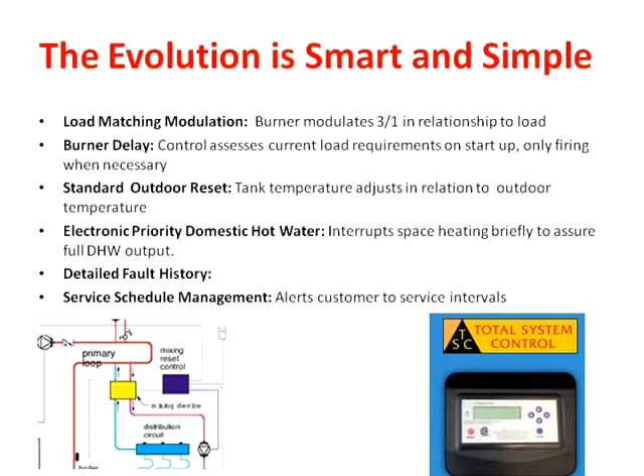This is both a smart and simple device. It's load matching modulation. The unit varies its burn rate in relationship to load, which has two sensors, high and low, on the tank in order to tell it what flame it should be working at. It has a burner delay, which is basically it looks at the load requirements and says, gee, do I really need to turn on or don't I? And very often the answer is you don't. It's the charm of having a high mass system. It takes a lot of the guesswork out of the hydronic system.